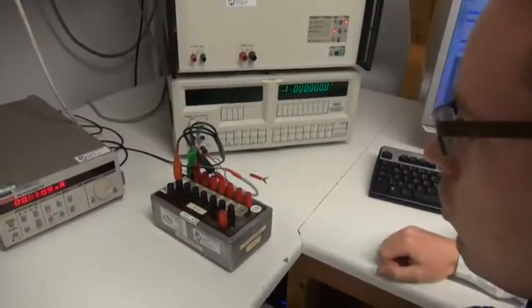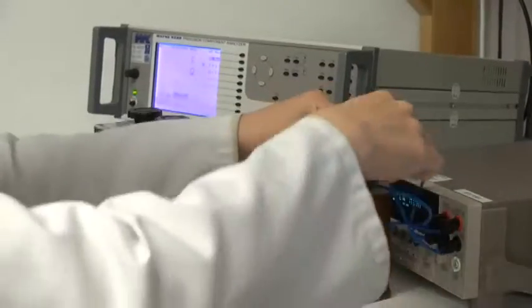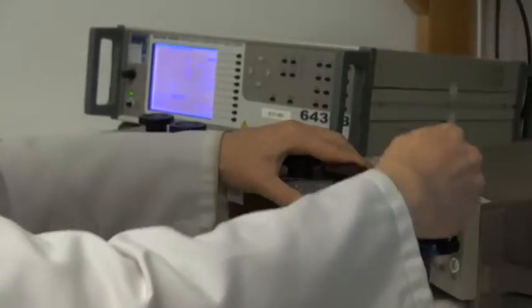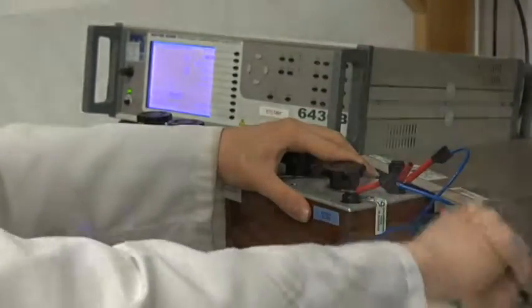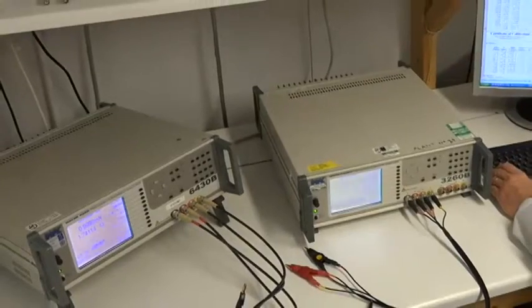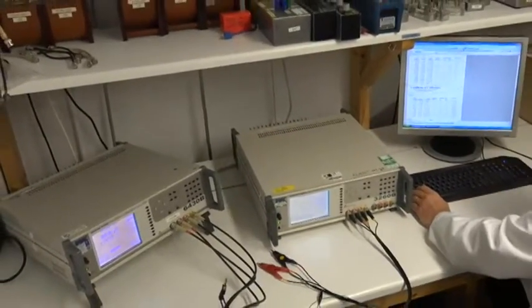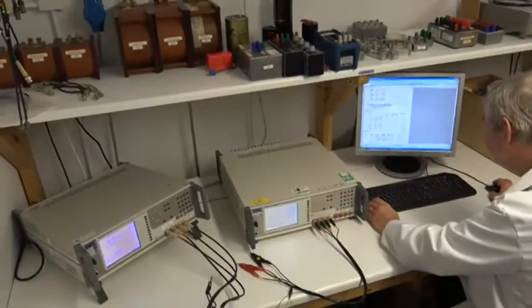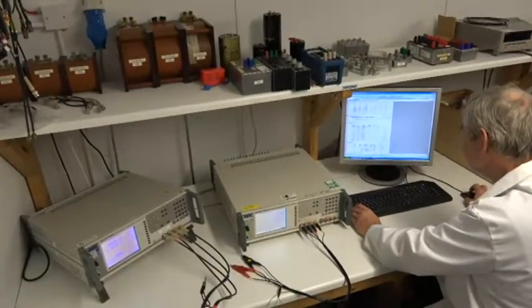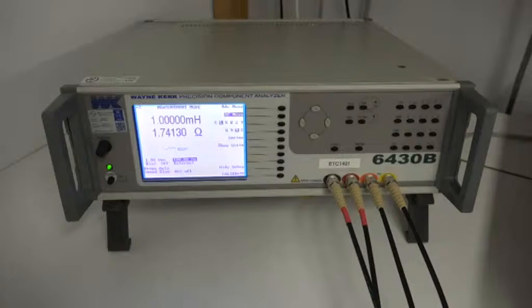We can measure voltages from nanovolts up to 30,000 volts and currents from femto amps up to 100 amps, from nano ohms up to tera ohms. We also measure capacitance and inductance with measurement traceability through our reference inductors and capacitors and a set of measurement bridges.